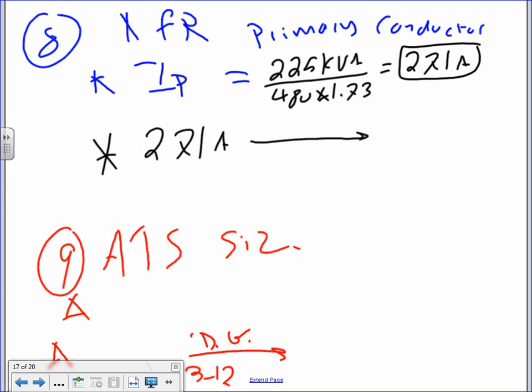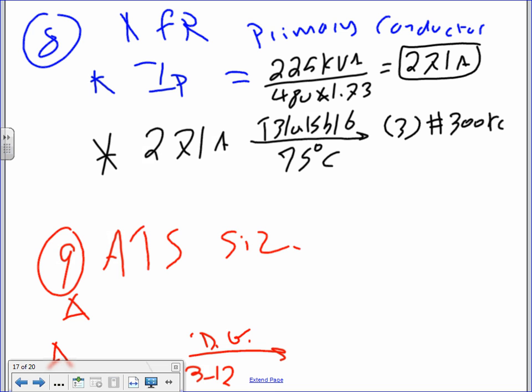Can you see the sheet? We don't multiply it by anything. We already took the 1.25 into consideration. Can somebody help me with Table 310.15(B)(16), 75 degrees? Can somebody give me the three conductors? It'll be three conductors. What's the size? 300. The 300? Okay. Any second?